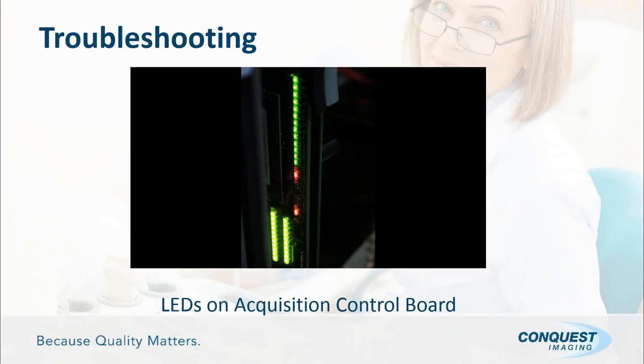And once it gets to the fully booted imaging mode, if it's not frozen, if it's actively scanning, that light will be solid as it just was. And the blinking light is the light number 2. Again, remember 0, 1, 2. The light number 2 is blinking at all times, and that means it's in a happy state. It likes where it's at. The bottom light is the one that you never want to see on, and that means there is an error. And at that point, you'll need to be troubleshooting what's going on with the acquisition control board. So the last light is the one that you should not see after boot up.